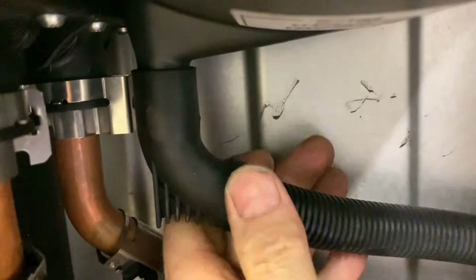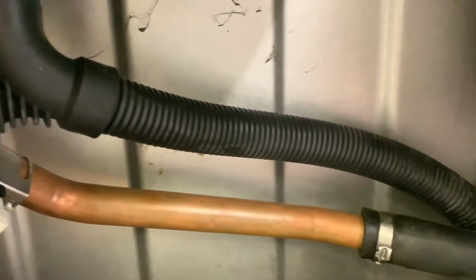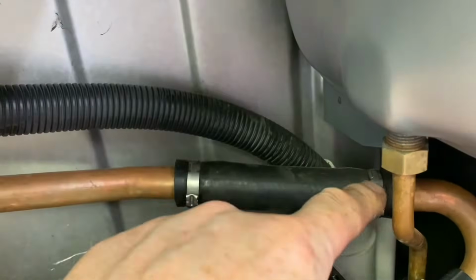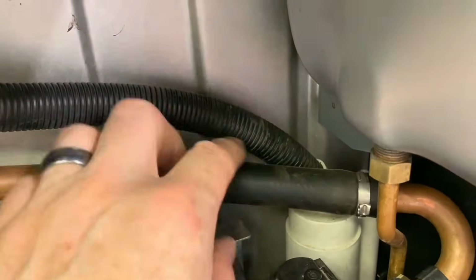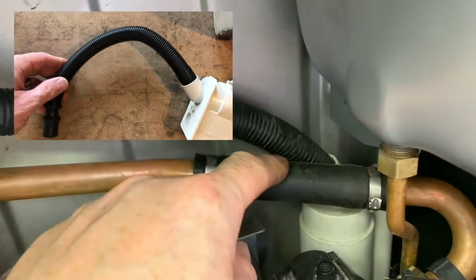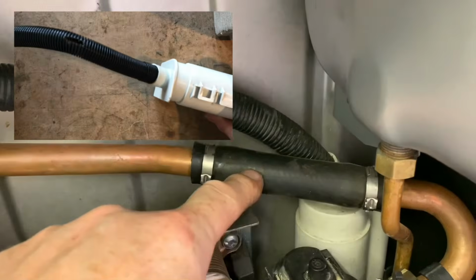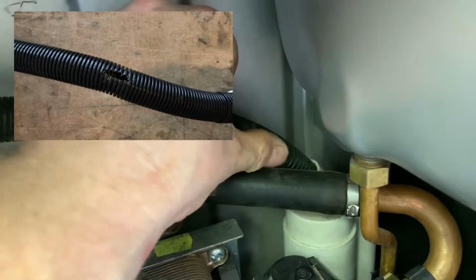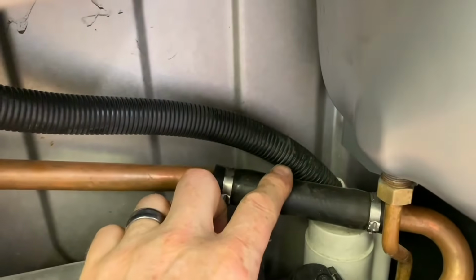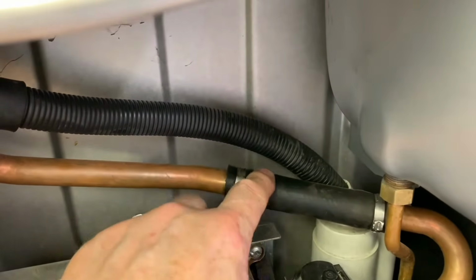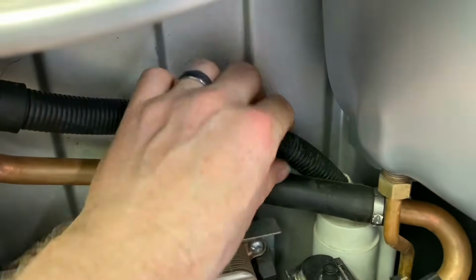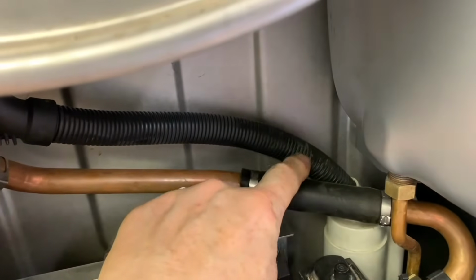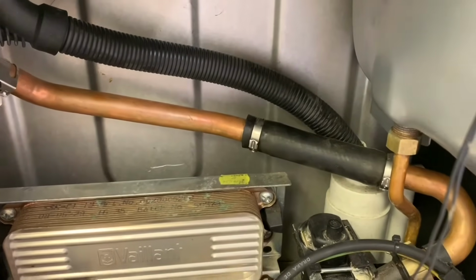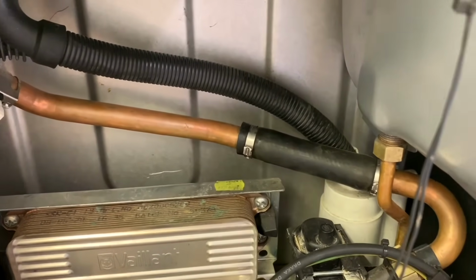Okay, now I've been to a few of these in the past where this has actually fallen off. So the fix for that one would be to put a Jubilee clip on it. Another one of the problems with this condensate pipe is you can see this is a rubber tube, and we'll talk about them in a minute, but when we change this to fully copper, because these are a problem, it's actually melting the plastic here. So Gas Safe issued a technical bulletin on this, so when you do service one of these old Pros or Pluses, you've got to make sure, if this is a copper pipe, that this plastic isn't touching it or it will melt, and the condensate will come through and will actually rot the bottom of the boiler out.